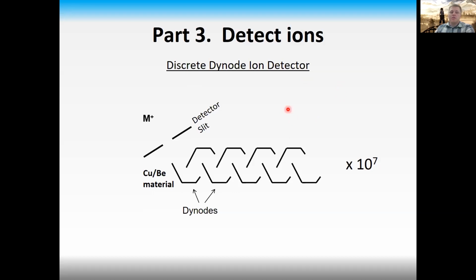And this is almost exactly the same as a photomultiplier tube, except in the first step, you don't have an electron or a photon interacting with some sort of metal with a low work function. Here you have your ion colliding with some material that lets off electrons real easy, and then you have that collide with more plates going down, and then finally to a transducer that sends your signal to your computer.